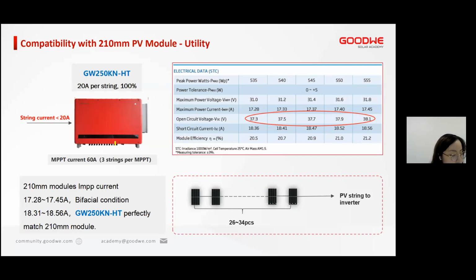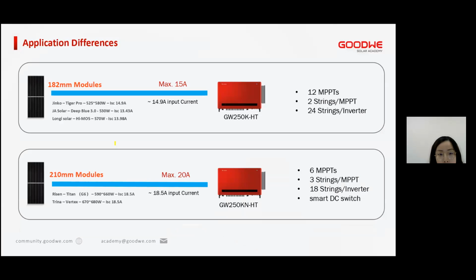Some customers may have the doubt that with a three input design, how should we deal with the backfeed current to the rest of the strings? Well, actually we use a smart intelligent DC switch with a no fuse design to solve this problem. So when an overcurrent failure happens, the DC switch can automatically cut off this current to prevent the backfeed current. Now let's compare the applications between 182 and 210 millimeter PV modules. We can see that the main difference is that it has a larger current capability and we use a smart DC switch design.